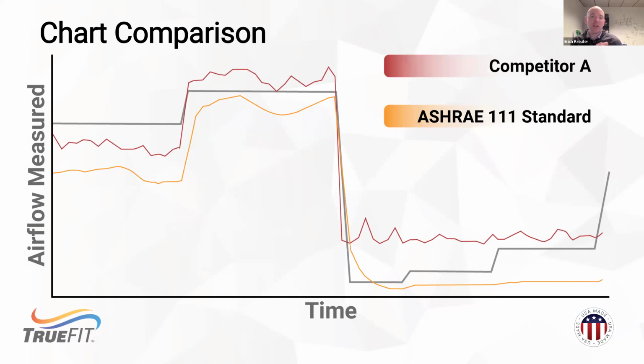So here, competitor A, this was thermal dispersion. This is following the trend, I'll say, on the first half of the chart. Again, when the damper is mostly open, my air velocities are high. And that's typically where these things would be calibrated, at a mostly open airflow.